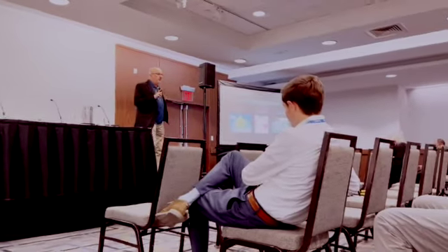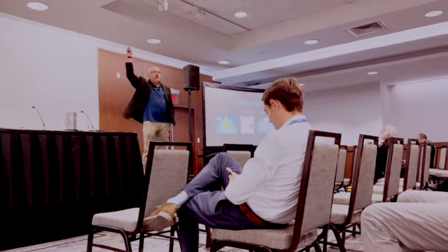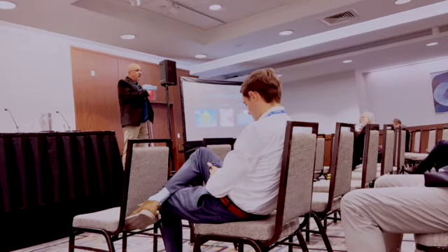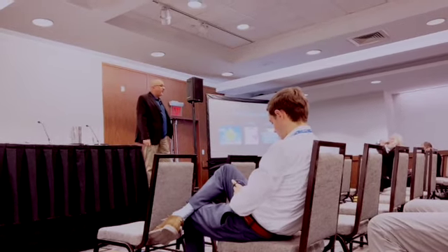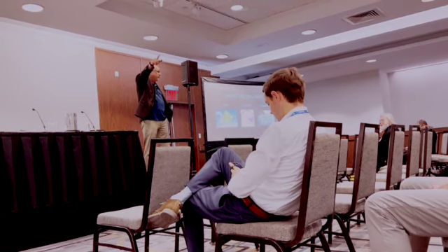Yes? Are you going to talk about zoning or grouping later? I'll talk about it now. I will tell you that we are not there yet on zoning and grouping. Actually, we can do grouping. And we can do addressing, but it's one way. So we can configure light fixtures and light bulbs to only respond to certain bit number commands, right? Which allows us to then say, okay, I can turn those 4 lights on, but not those 4, and they're all in the same circuit.